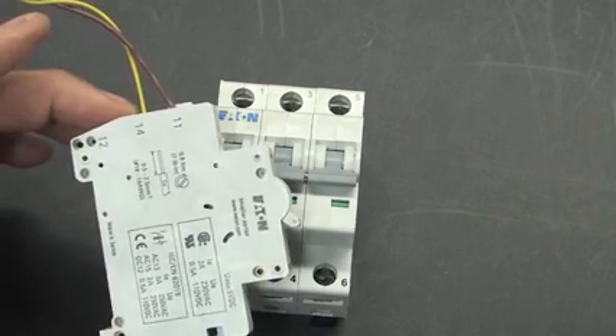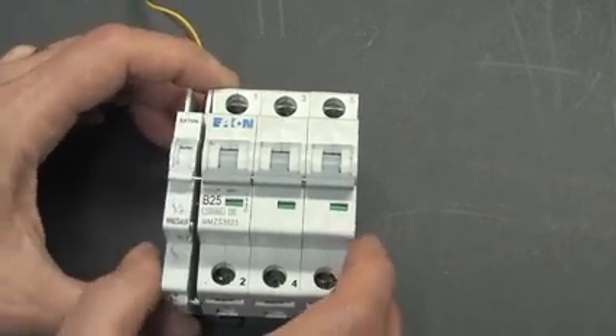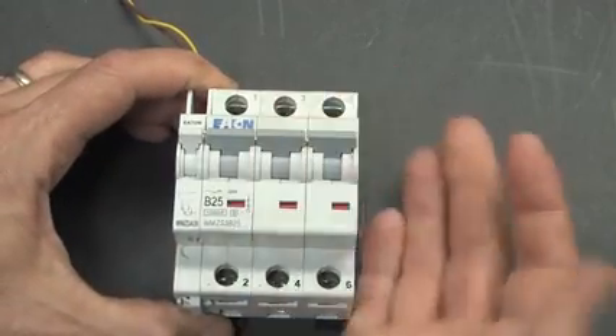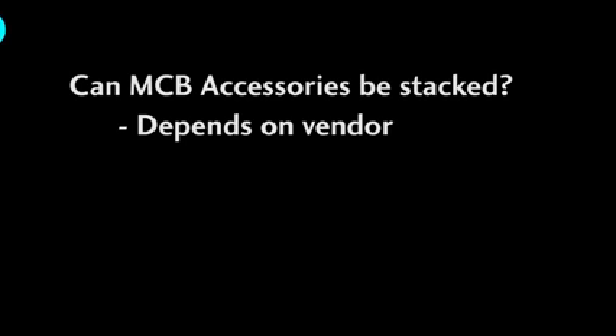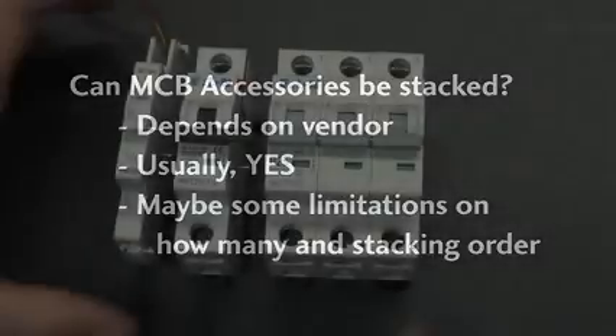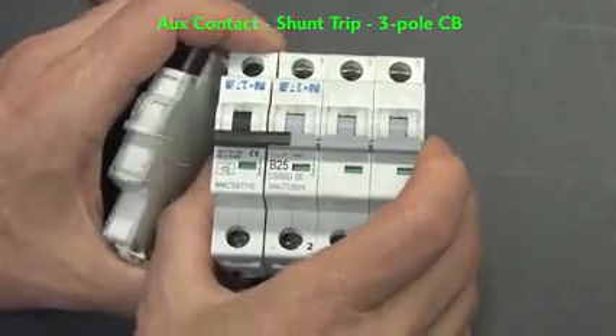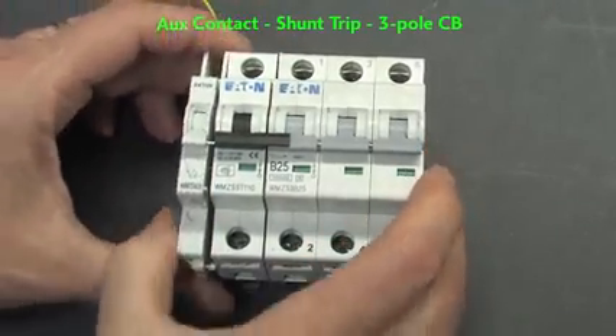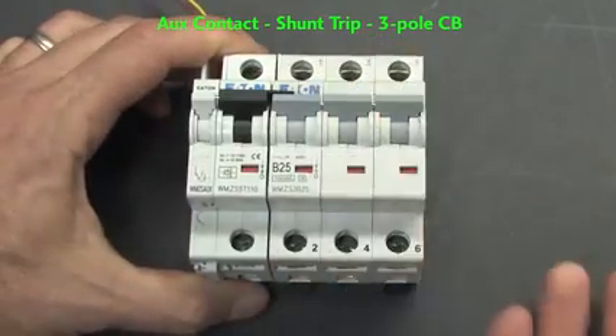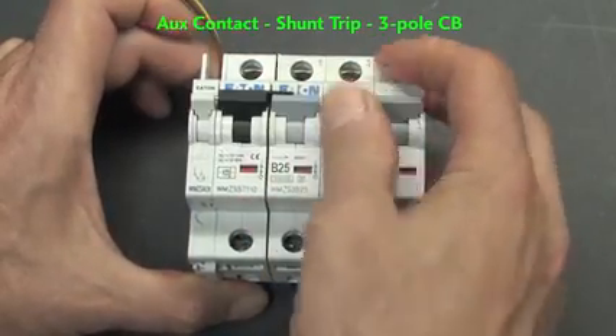An aux contact gives the PLC a way to monitor the status of the breaker. Here's an example of an MCB aux contact. It just clips on here, so when the breaker trips, this contact closes. Can you stack these MCB style accessories? Well, it depends on the vendor, but usually the answer is yes. For example, here's a shunt trip and an aux contact stacked on a 3-pole breaker. Now we can remotely trip the breaker and monitor its status.